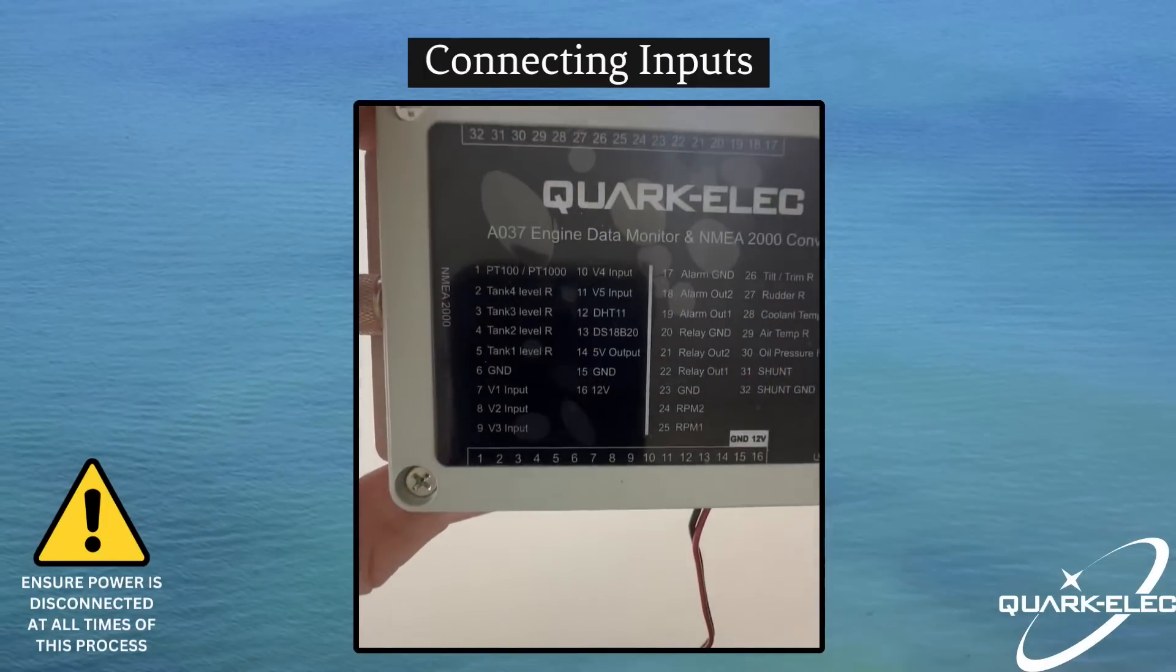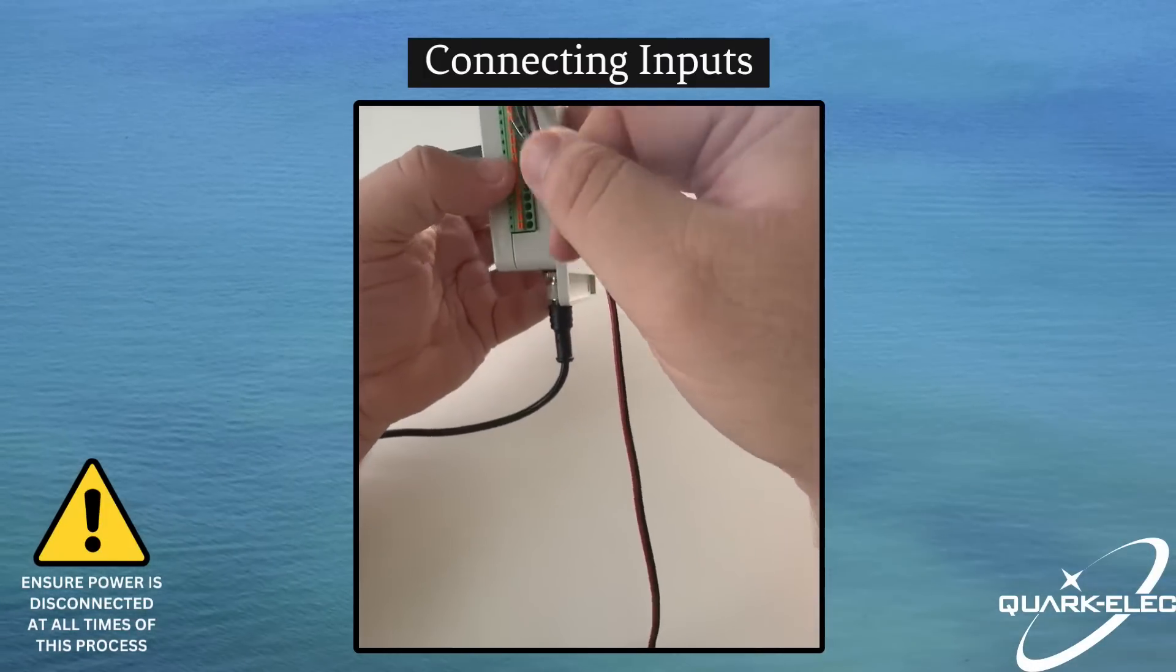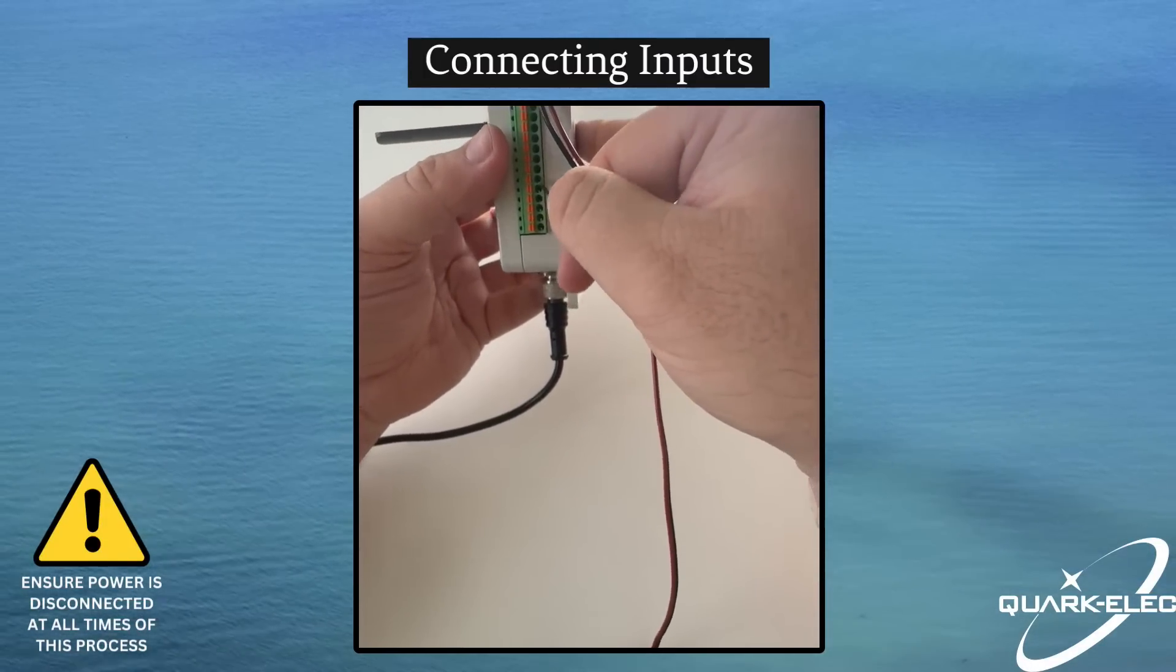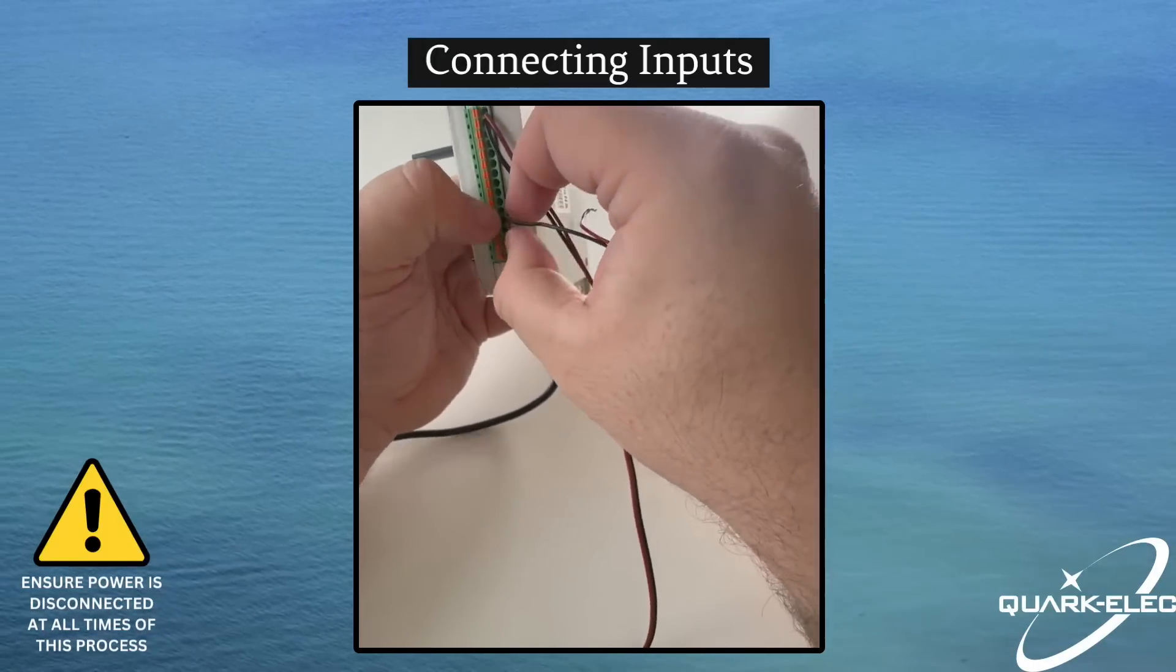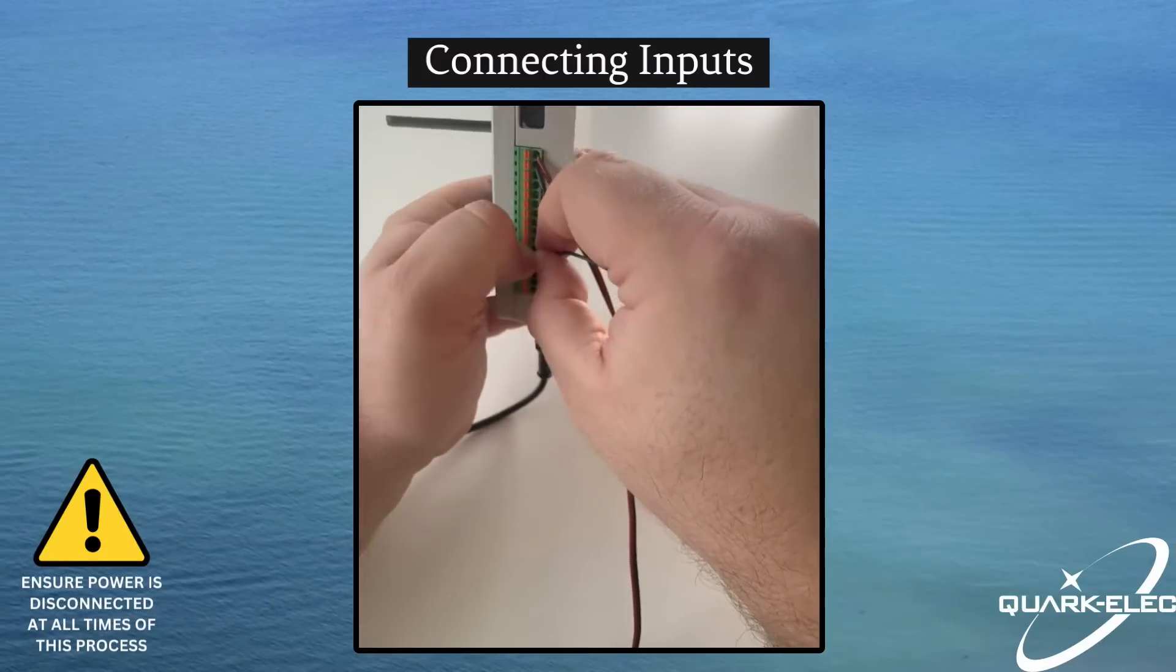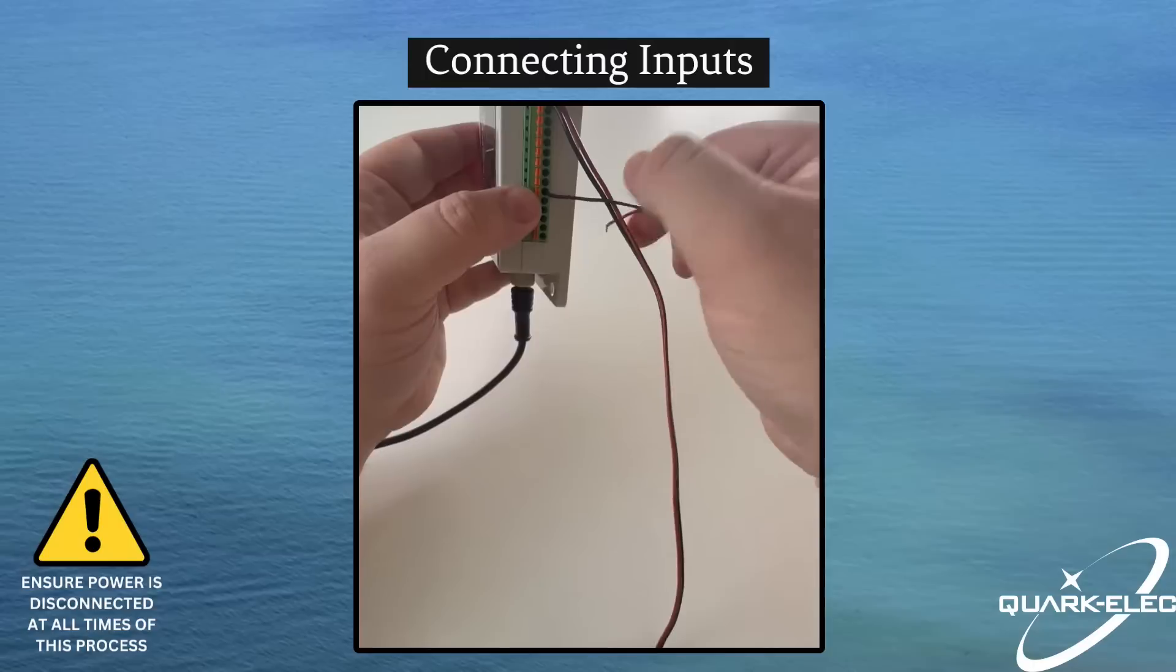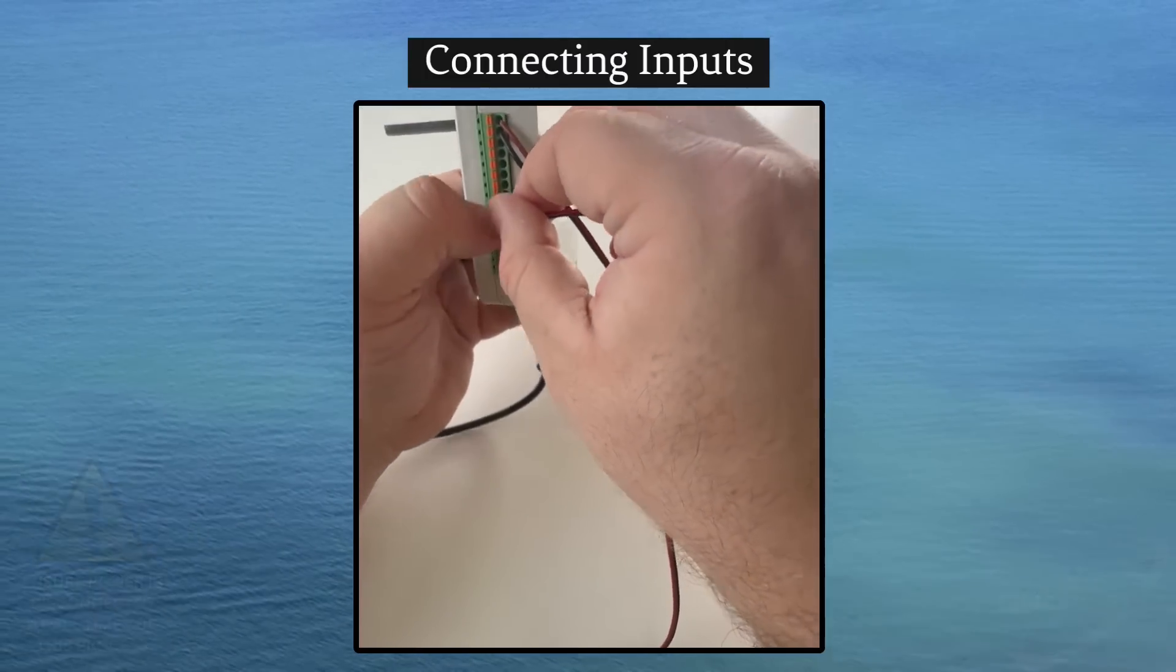When connecting inputs to the A037, you must locate the correct pinout that you'll require. In this case, it will be pinout 6 for the ground and pinout 7 for the positive or data wire. Simply push the tab on the relevant pinout, insert the cable and release the tab. Again, ensuring that a secure connection has been made.